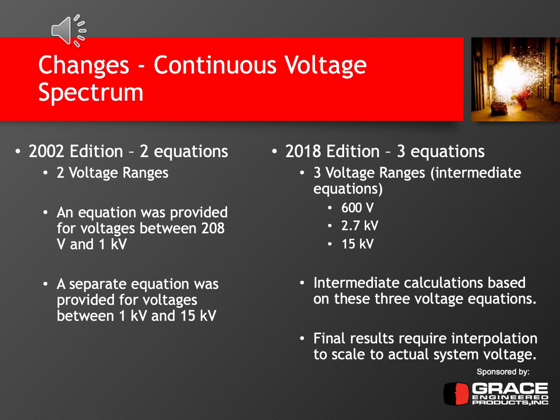And then you need to calculate each of these equations, because for the final values, the minimum currents, these equations are needed in the next step. Then there's some guidance, based on whatever voltage you have, on which of those final equations you use as your final arcing current. And like I said earlier, the final results require interpolation to scale to the actual system voltage if it differs from these three voltage ranges.